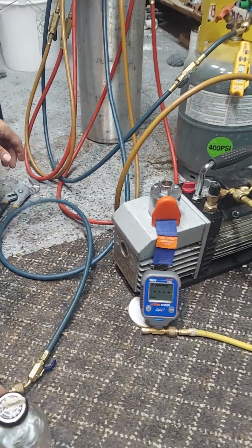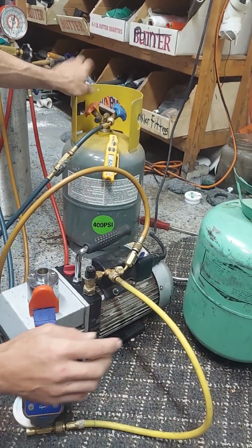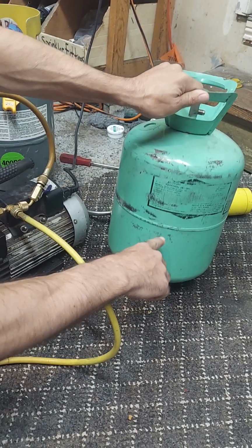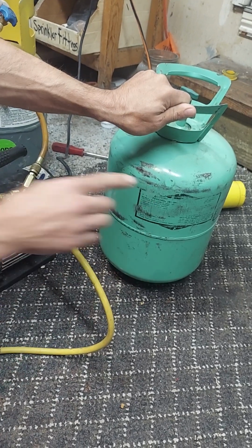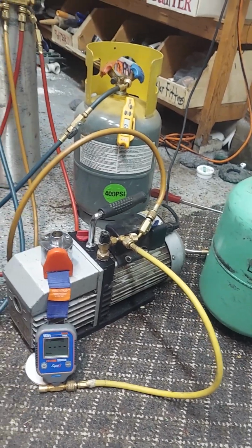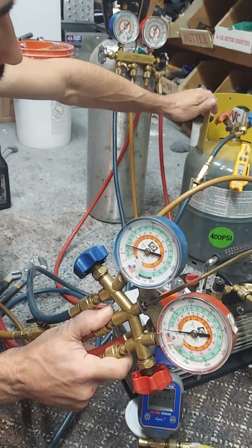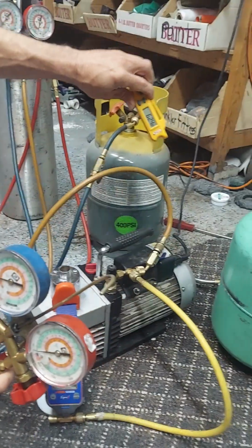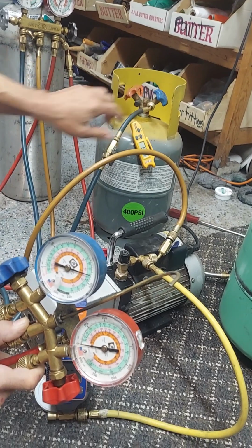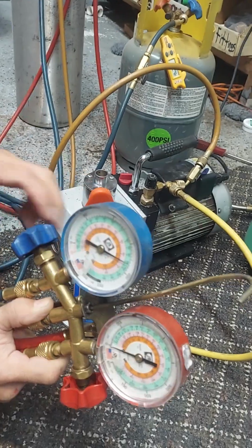Relating to that, if I come over to a tank, as long as I have a little bit of liquid in the bottom, let me show you on this one. If I have a little bit of liquid on the bottom, or 30 pounds of liquid, it doesn't matter. It's going to follow the same temperature pressure chart. I don't know what liquid is in this one, to be honest. We're about to find out. So it's about 62. This might be a little warmer because we had a temperature drop, so maybe 65. Let's see. 65, pink. So that would be R410A.